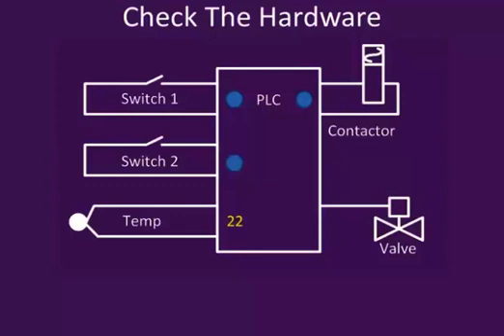Analog inputs, such as the temperature, are best checked through the software. Firstly, you have a look at it and check that there is a value. Then you disconnect it at the sensor. If everything's okay, the wiring's okay, the value should go away. It'd go to 0 or negative or something. Then you reconnect it and the value should come back. You should do this well before calibration time because the sensor may need to warm up.